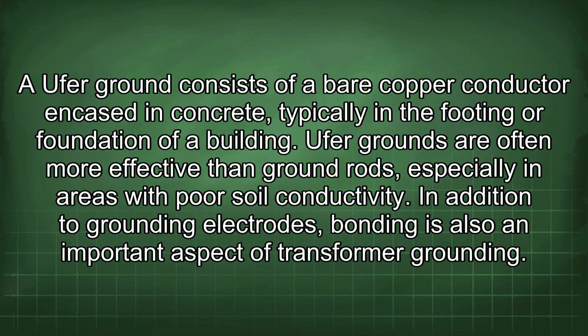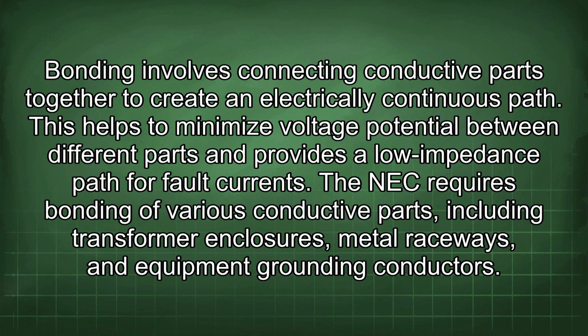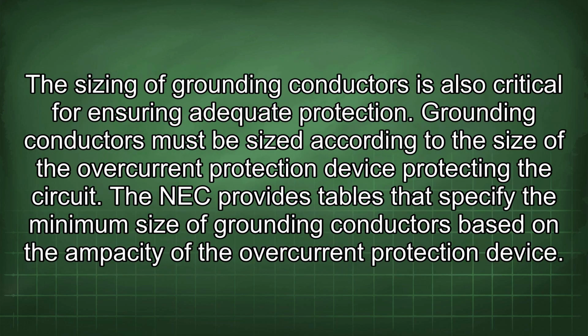In addition to grounding electrodes, bonding is also an important aspect of transformer grounding. Bonding involves connecting conductive parts together to create an electrically continuous path. This helps to minimize voltage potential between different parts and provides a low impedance path for fault currents. The NEC requires bonding of various conductive parts, including transformer enclosures, metal raceways, and equipment grounding conductors. The sizing of grounding conductors is also critical for ensuring adequate protection. Grounding conductors must be sized according to the size of the overcurrent protection device protecting the circuit. The NEC provides tables that specify the minimum size of grounding conductors based on the ampacity of the overcurrent protection device.